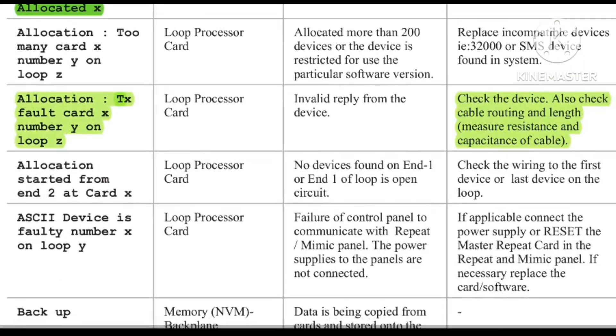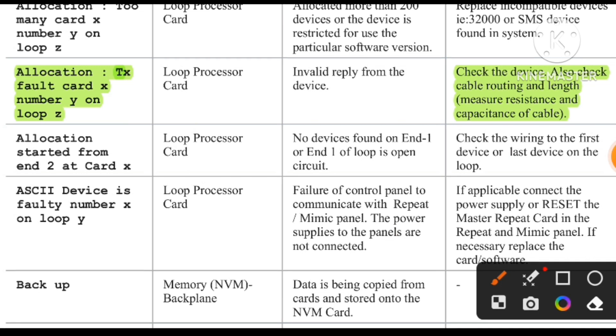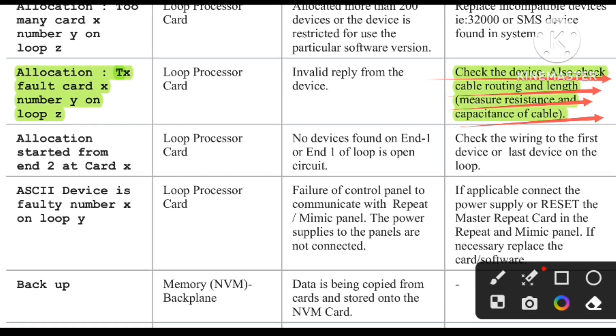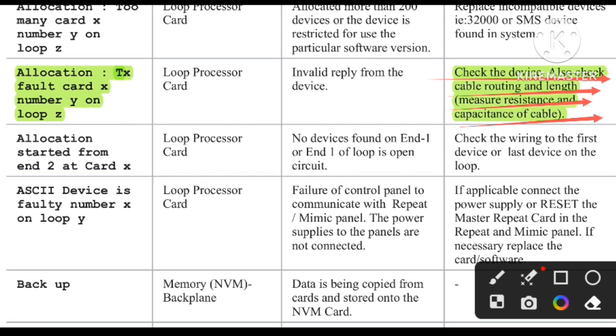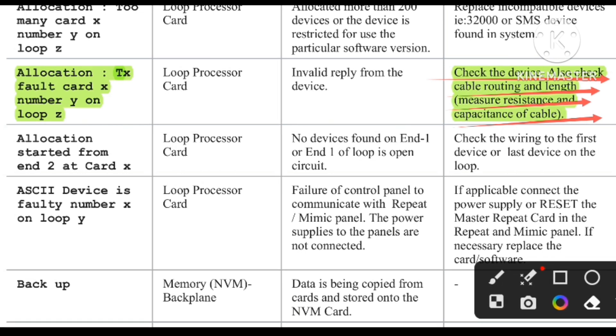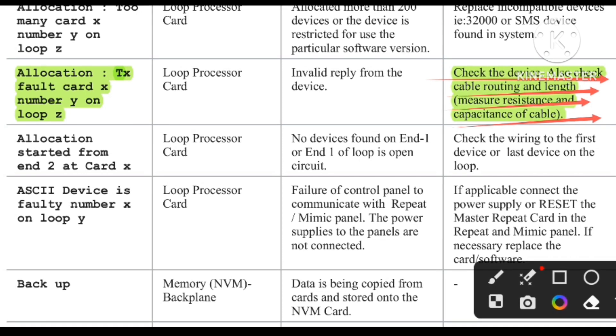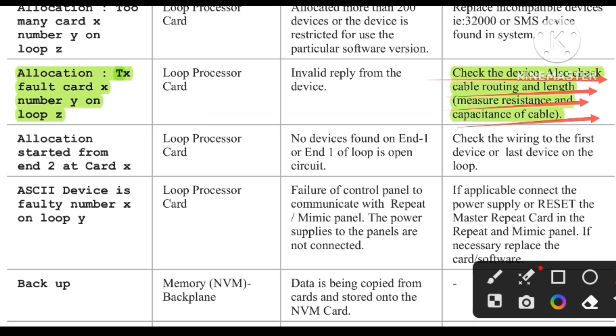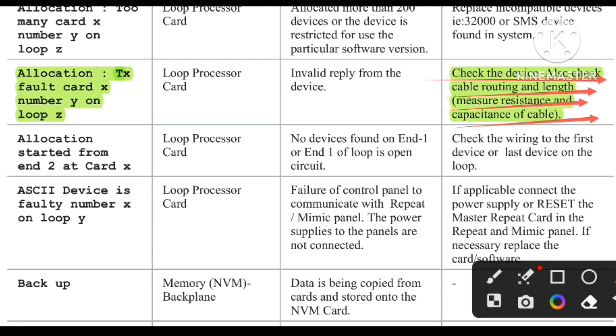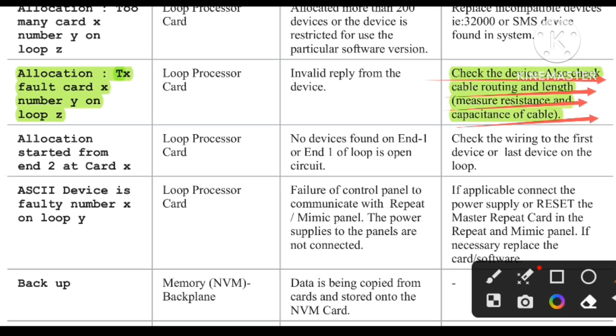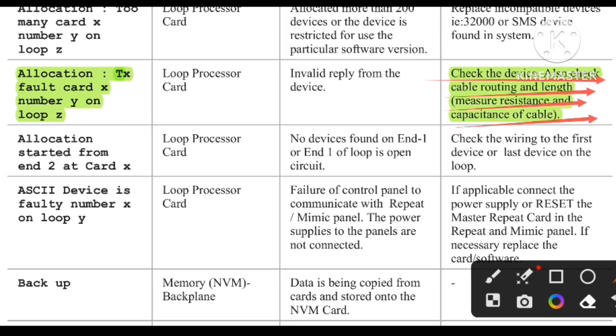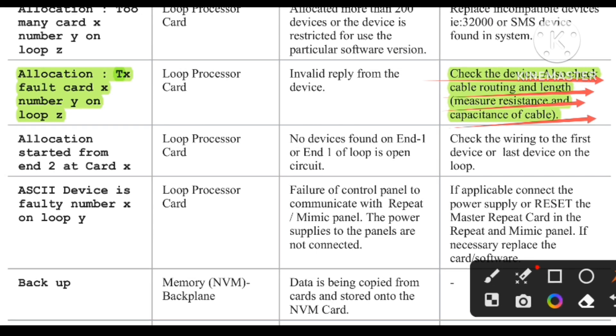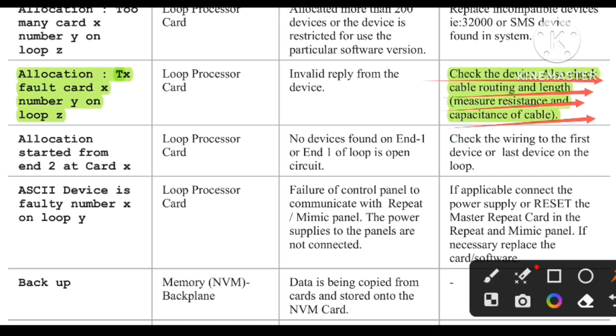For the TX fault, check the device, check cable routing, measure cable resistance and length, because loose connection can cause high resistance. This is a communication fault — the device is not communicating with the panel, similar to an open circuit fault. To solve this, remove the return cable from the panel and check at which position the loop is mapped or allocated.